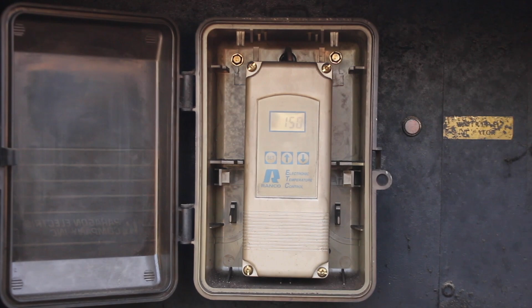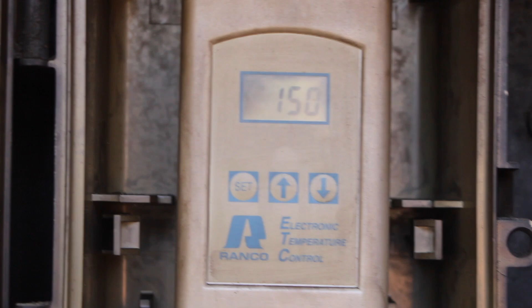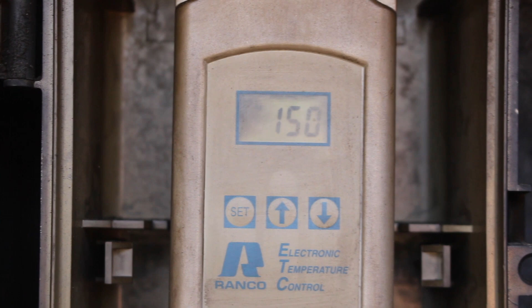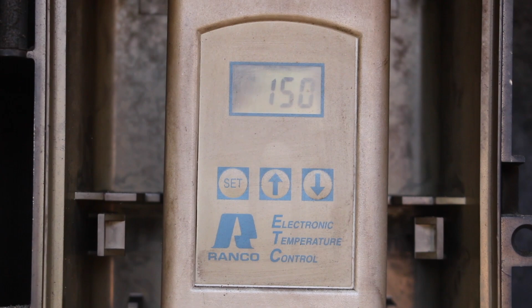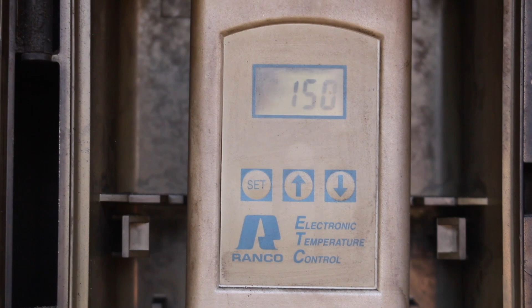Here's the thermostat, and right now it's showing 150 degrees, which is the water temperature in the 160-gallon bladder above the firebox. The thermostat tells the fan blower when to kick on and off. When the water temperature drops below 155 degrees, it kicks the fan on and gets the fire going really hot until the water reaches 160 degrees. At 160 it cuts back off, and it just continuously cycles like that.